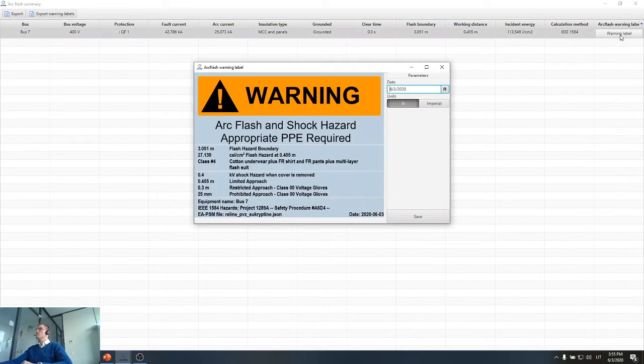So we have a warning label, which should be used and stuck to the panel in order to inform a person who is working with the electrical network about the possible damage, about the possible dangers. You can see that the flash boundary, as I have said, is 3 meters, and in order to work with this kind of network, we have a recommendation to use class 4 personal protection equipment. It would include cotton underwear plus a fire-resistant shirt plus fire-resistant pants, and also a multi-layer flash suit.